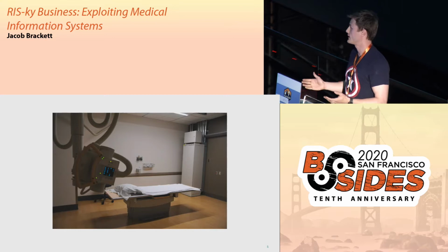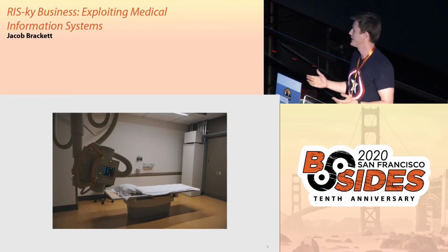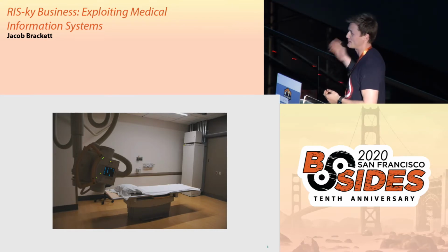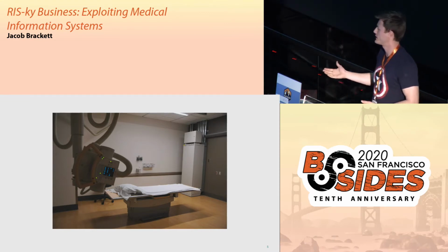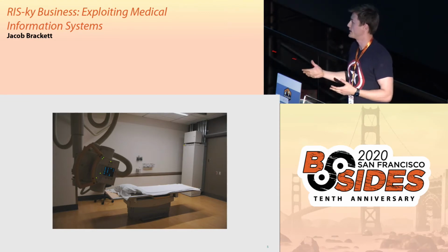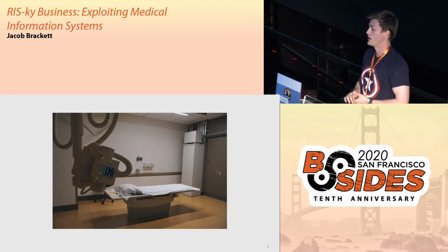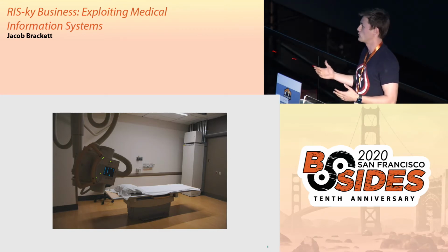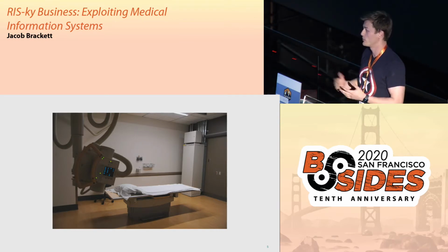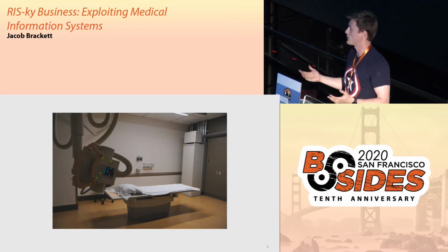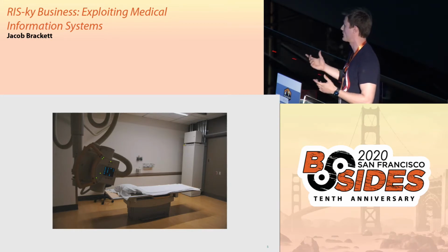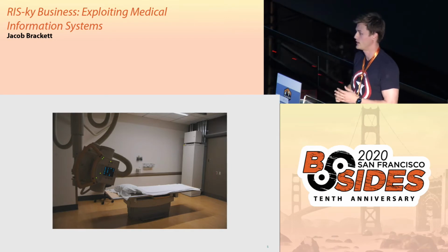Great, so let's say you are a hospital and you've purchased one of these for the first time. This is an X-ray. It's meant to do chest X-rays. The patient lays down and they make an image of the patient's chest. You've set up your room. You've got lead-lined walls. You may notice something might be missing from this picture. There's no place for a doctor to actually go in and take a look at the image that came out. All there is, kind of the camera, if you will, is the X-ray device itself.